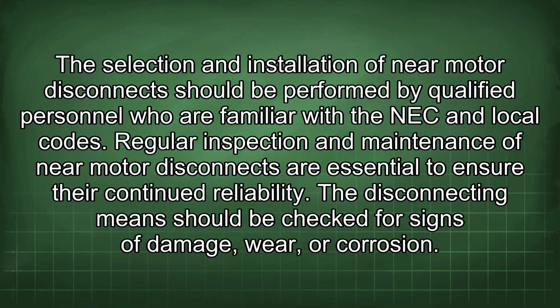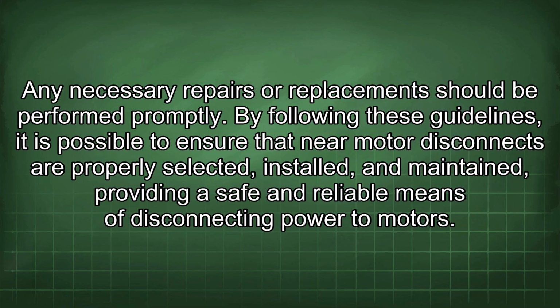Regular inspection and maintenance of near motor disconnects are essential to ensure their continued reliability. The disconnecting means should be checked for signs of damage, wear, or corrosion. Any necessary repairs or replacement should be performed promptly. By following these guidelines, it is possible to ensure that near motor disconnects are properly selected, installed, and maintained, providing a safe and reliable means of disconnecting power to motors.